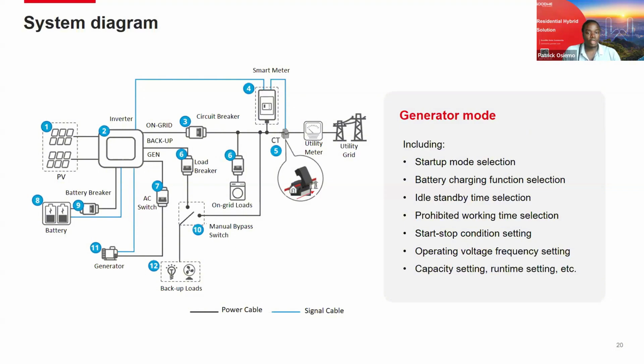It has 3 AC ports, so we can support on-grid loads, backup loads, all the critical loads, and similarly, the generator can connect to the inverter itself. Because it's a hybrid inverter, you can see the strings also connecting to the inverter and the low voltage batteries also connecting to the inverter. In case the grid fails, the inverter can switch in less than 10 milliseconds to backup power, so power from the panels and power from the battery supply the critical loads, the loads connected on the backup port. If the battery state of charge reaches a certain level, let's say 20%, the inverter is able to send a start signal to the generator, and the generator will pick up and supply power to the on-grid loads. The same generator can also be used to charge the batteries.